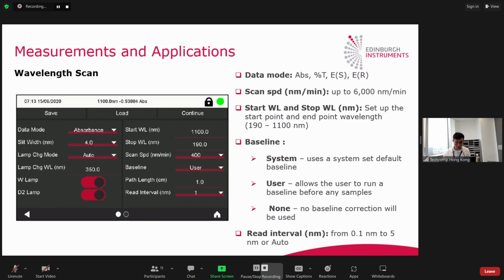And one more key thing I want to talk about is the baseline. You can choose from several baseline options. One is the system, which means you use the system as the default baseline. Or you can choose the user baseline, where you measure the baseline manually before any measurements. Or you choose none, which means you don't want baseline corrections. You can also select your interval width from 0.1 nanometer to 5 nanometers, or you can choose auto, and then the instrument will automatically choose reading intervals for you.